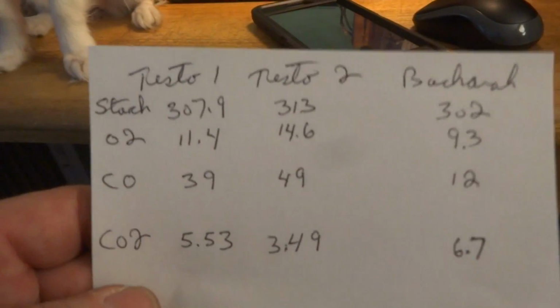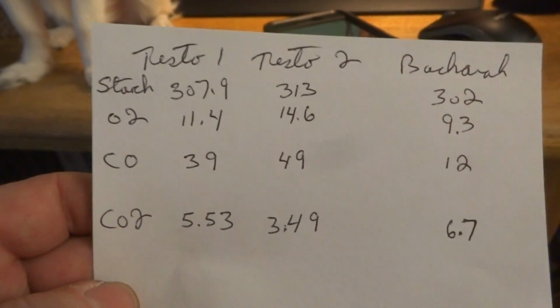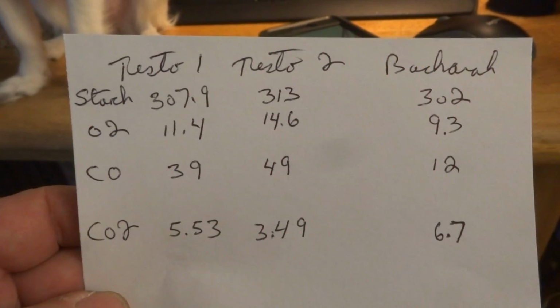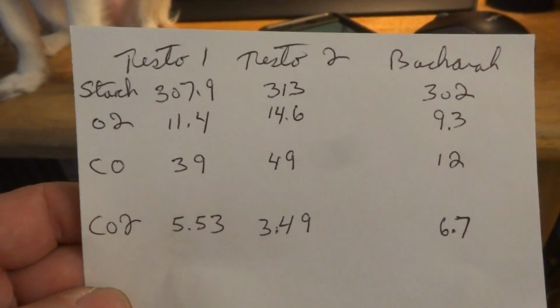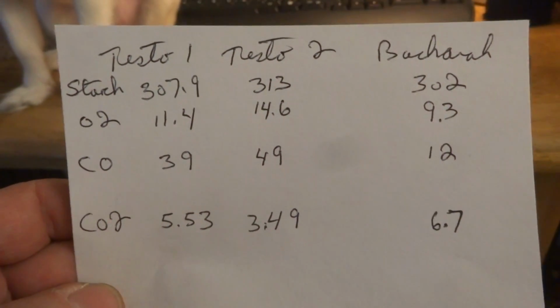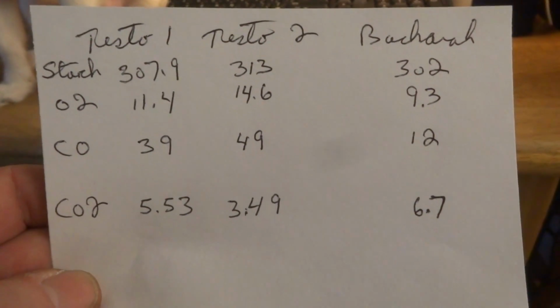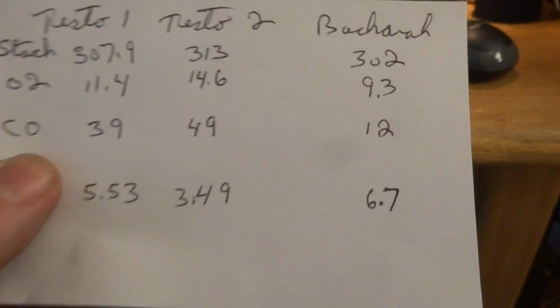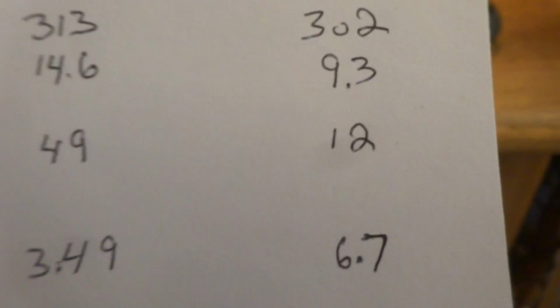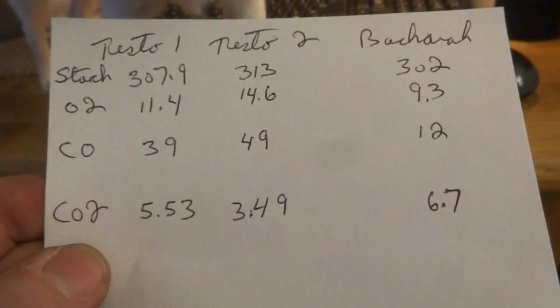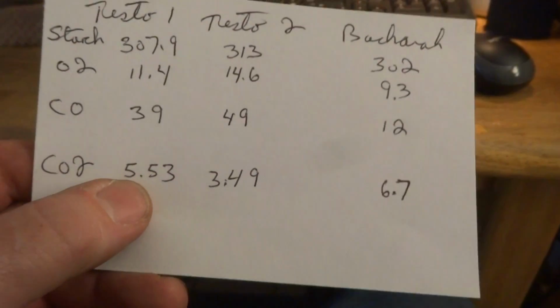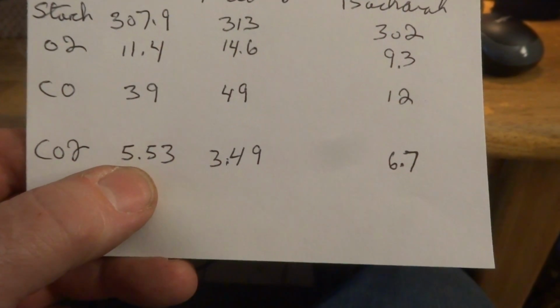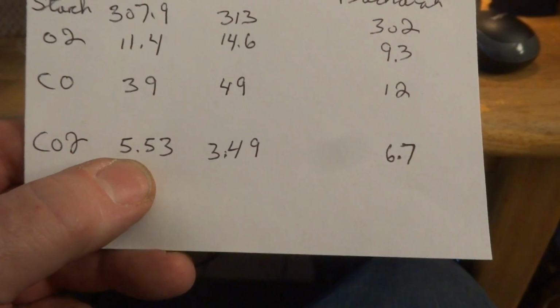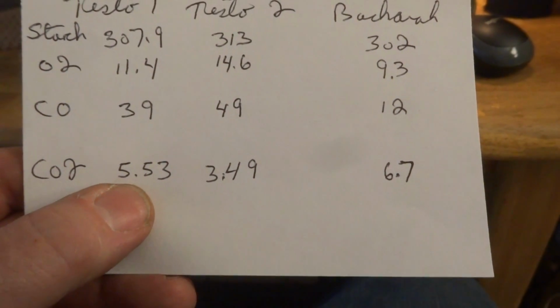But anyway guys, here's a shot of the stuff - the Testo 1, Testo 2, and the Bacharach. So the only thing I really got a major issue with is the CO. See, the CO is only 12 on that - you'd figure it'd be higher. The rest isn't so bad. The CO2 is pretty close, within 1 point.